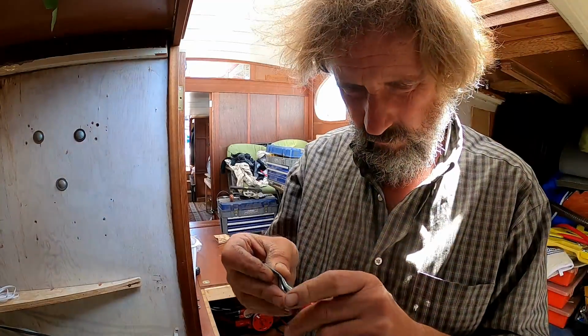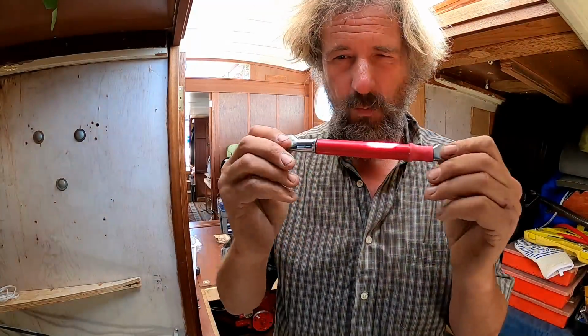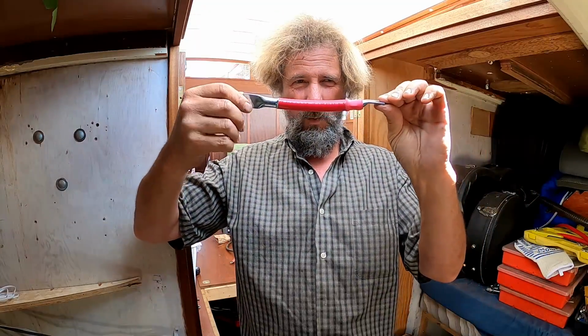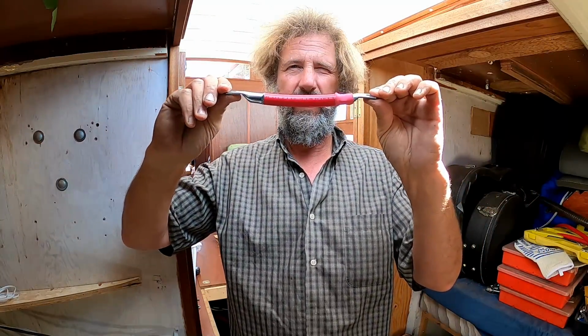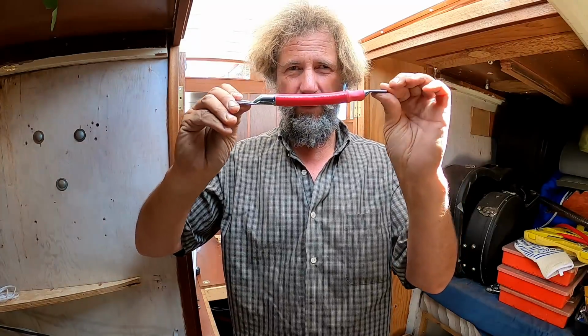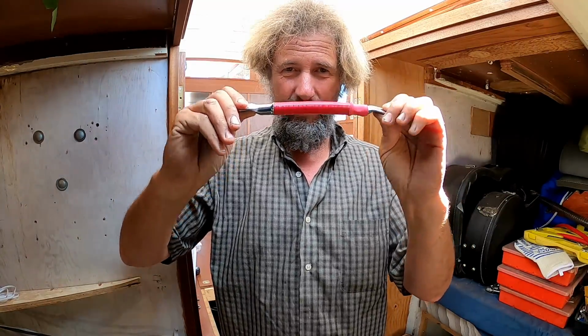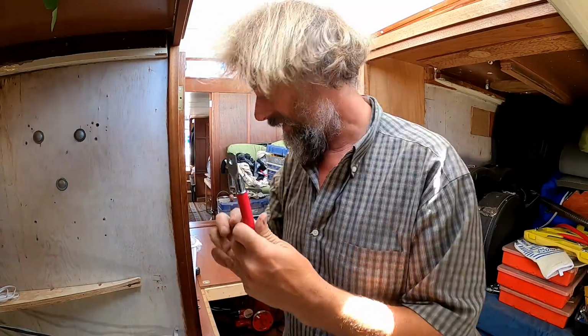And on with the lug. Okay, now when you're setting up cables, especially short ones, make sure that you orient the lugs the way they're going to be in use, because this cable is remarkably difficult to twist. If you'd put it together this way and expected to twist it to that way in the battery case, you'd be sorely mistaken. So try to get them close.